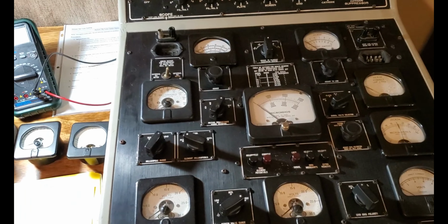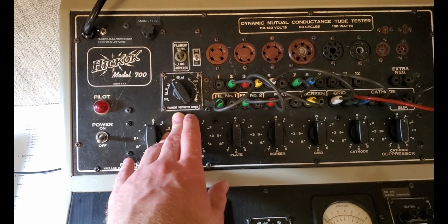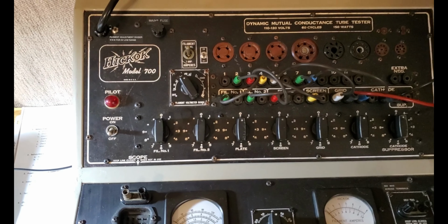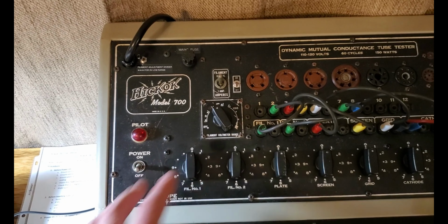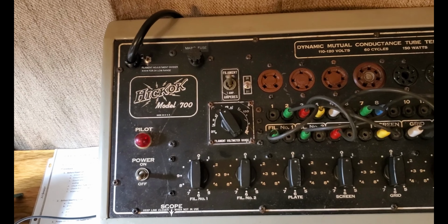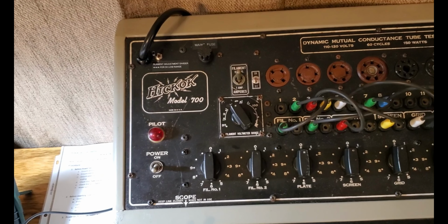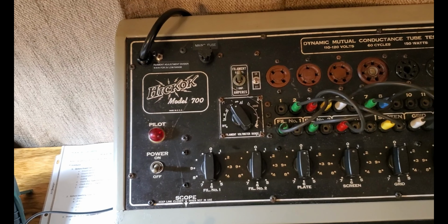And then one of the other issues we had was a broken wafer switch here for the tube voltage range. This switch is a wafer switch with, I think, four wafers, and each wafer has two sides, a top side and a bottom side, with different contacts and different switching poles as you turn the switch. So basically the switch has 8 different pole decks. It's actually quite complicated, the switching arrangement of this. And 2 of the wafers, so 4 decks, essentially were broken off of the wafer switch. It got smashed from the backside and cracked.